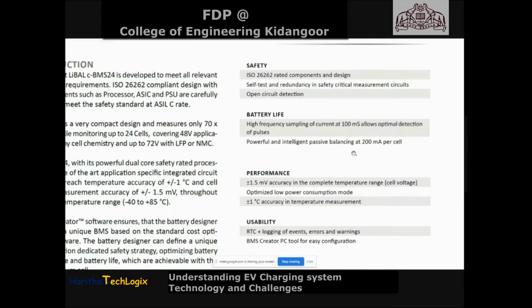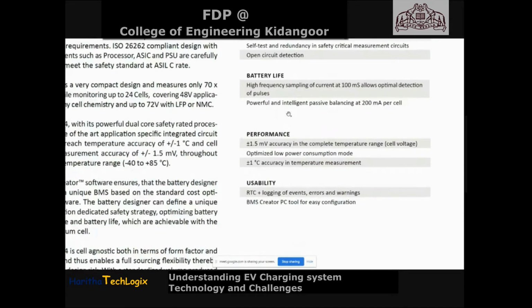You can see the passive balancing at 200 milliampere per cell - that is the amount of supply it can provide. And at the end of the day, the performance, that is the accuracy of this BMS, is plus or minus 1.5 millivolt. And the temperature measurement accuracy is plus or minus 1 degree Celsius. So that's where this BMS comes in.